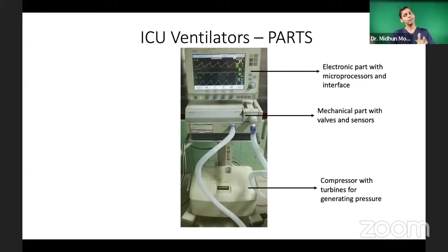Now, whenever we are connecting a patient to the ventilator, I already told you that whenever we increase the pressure, the volume increases. More PMUS means more volume comes, right? So you have seen that pressure and volume are sort of connected. Whenever we put the patient on the ventilator, I can control only either the pressure or the volume. In a ventilator, we control the volume by controlling the flow, because flow is almost the same as volume, only the time part differentiates them. Flow into time will give you the volume, right? Volume control ventilation or flow control ventilation, both are the same thing.